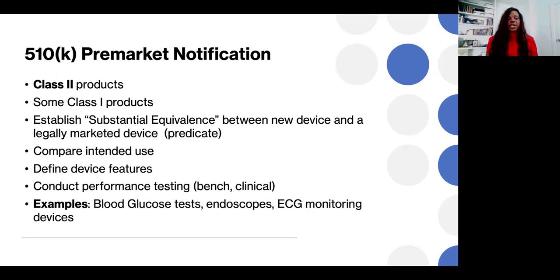For a 510(k) pre-market notification, I mentioned that these are for class 2 products and some class 1. For this type of application, we want to establish substantial equivalence between the new device and a legally marketed device, which is called a predicate. We would compare the intended use of our new device to the device that's already on the market. We have to define our device features, and we have to conduct performance testing, such as bench studies and clinical studies.